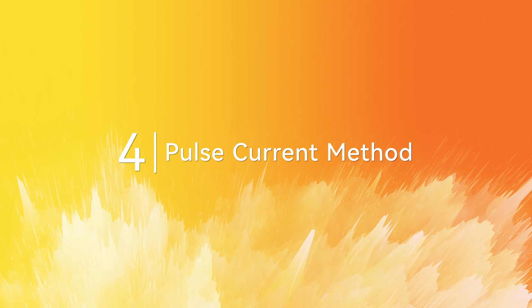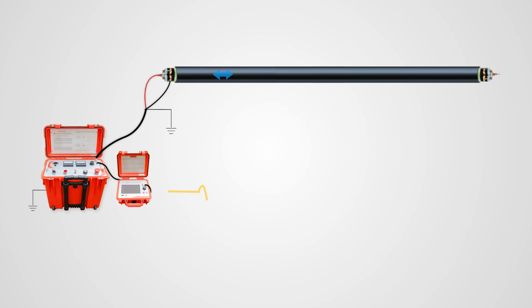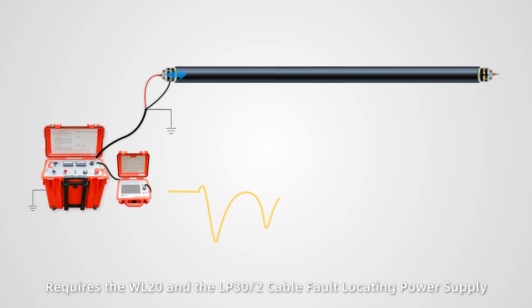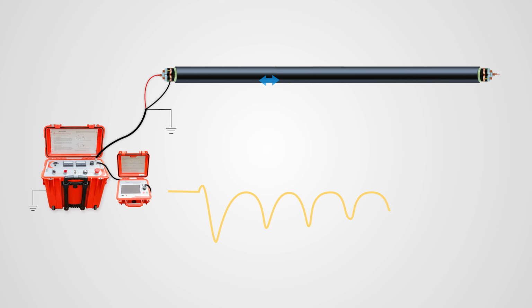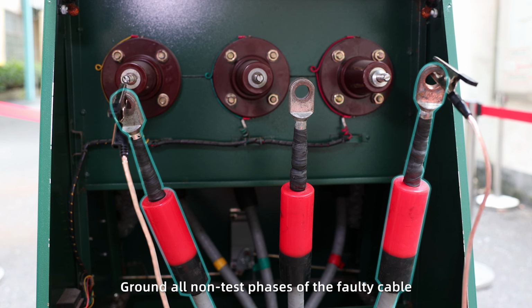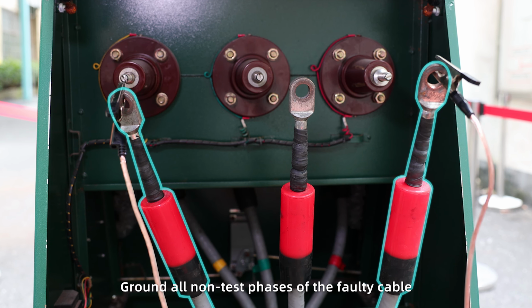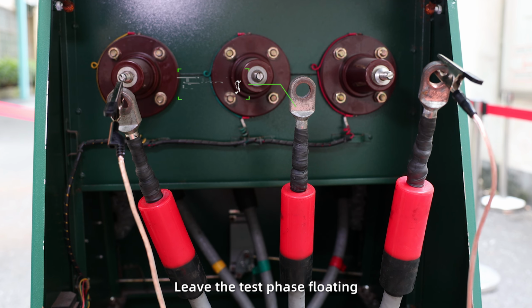4. Pulse current method. Used for testing high-resistance cable faults. Requires the WL20 and the LP30/2 Cable Fault Locating Power Supply. Ground all non-test phases of the faulty cable. Leave the test phase floating.